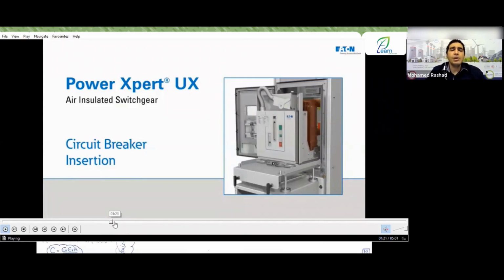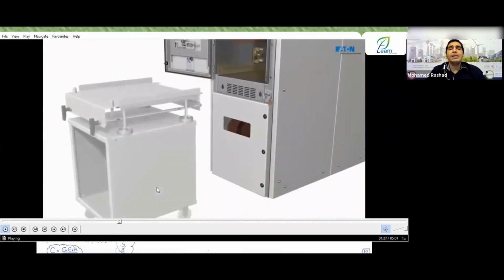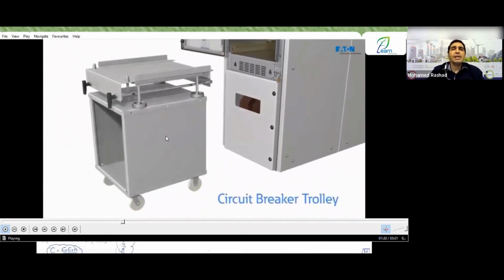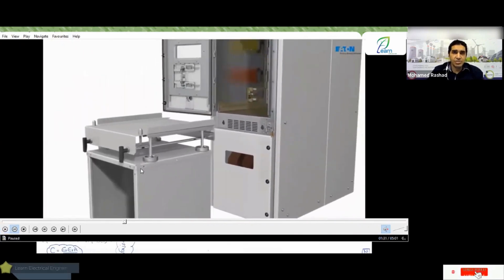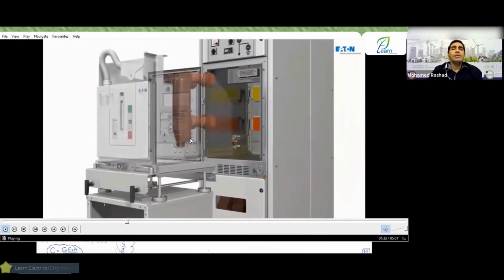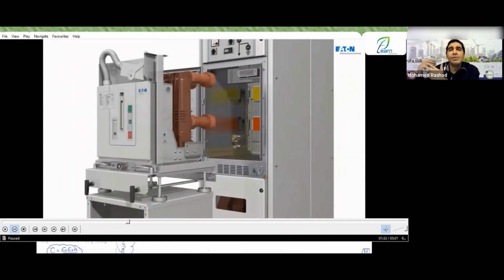All right, what does the term withdrawable circuit breaker mean, engineer? It means a breaker that can be withdrawn. Here I have something called a trolley, just like a children's trolley, and it has wheels. The breaker is mounted on it. In the position you see here, the breaker is disconnected from your panel so that you can perform maintenance operations.